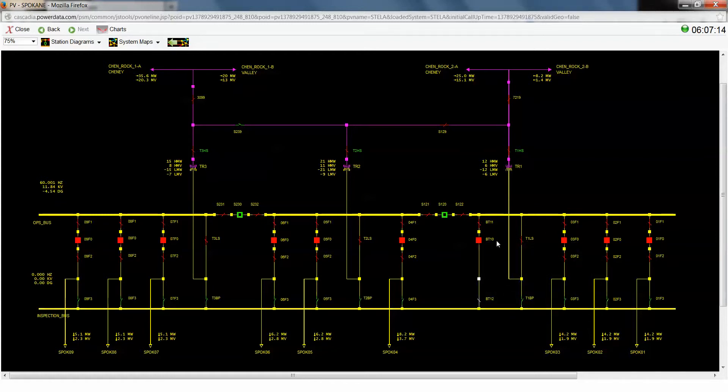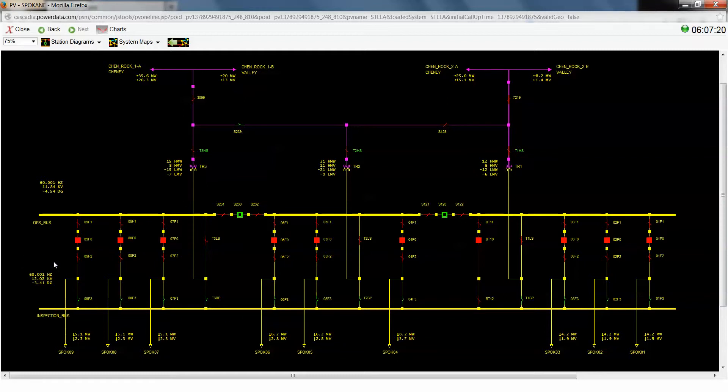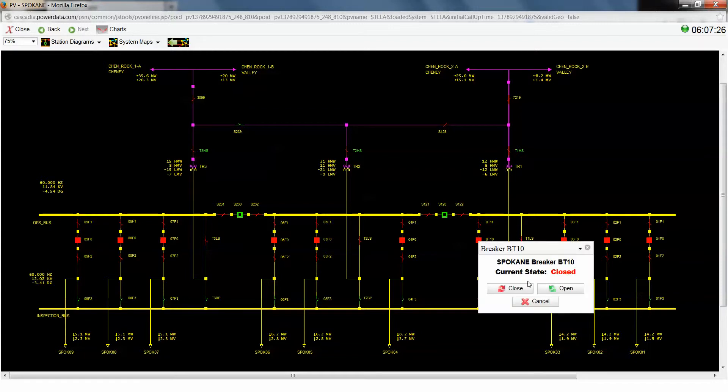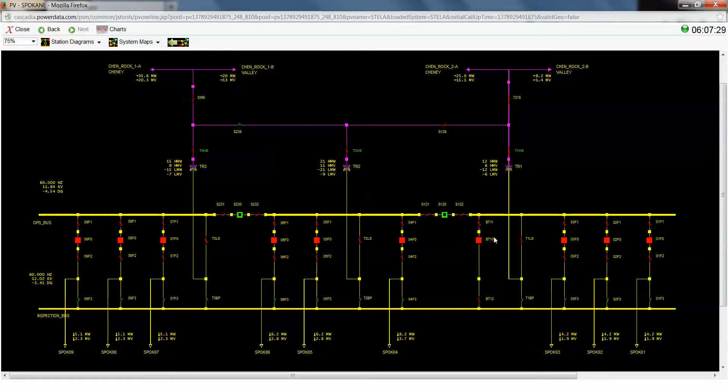So we're going to close this bus tie breaker. Alright, you'll see that our inspection bus has been energized and we're up to about 12 kV, which is what we should be for this system. Alright, so now that we've tested that, we're going to reopen our bus tie breaker.